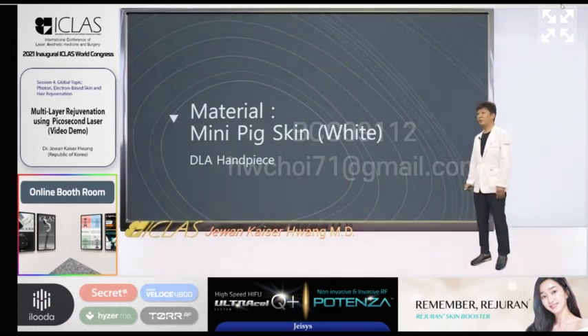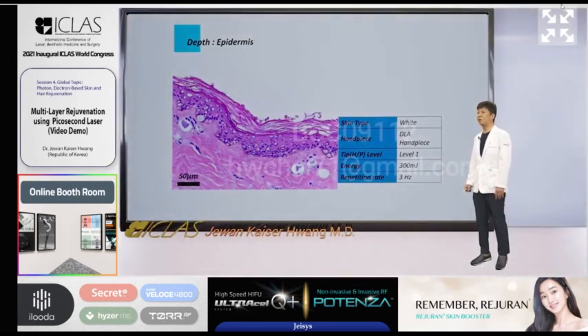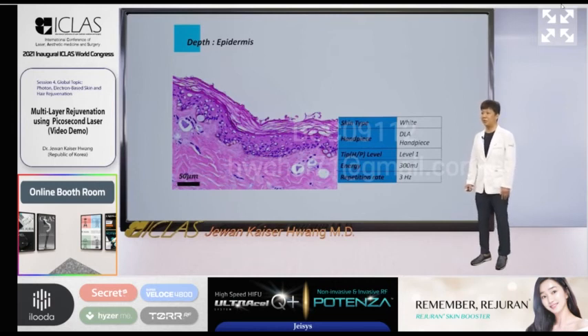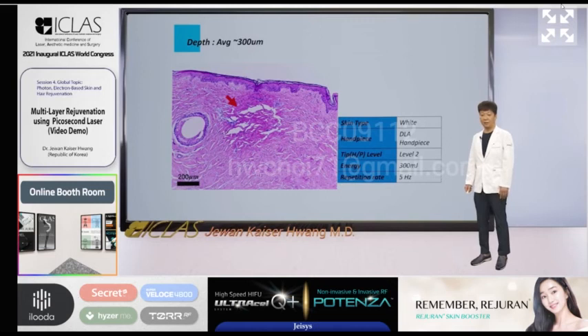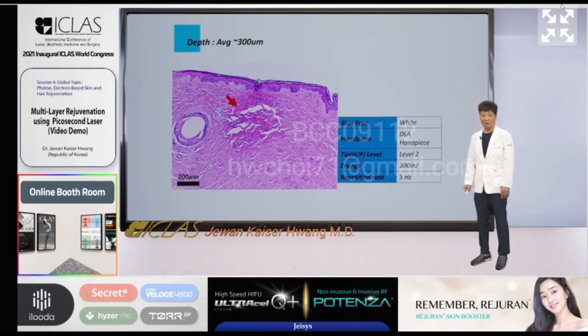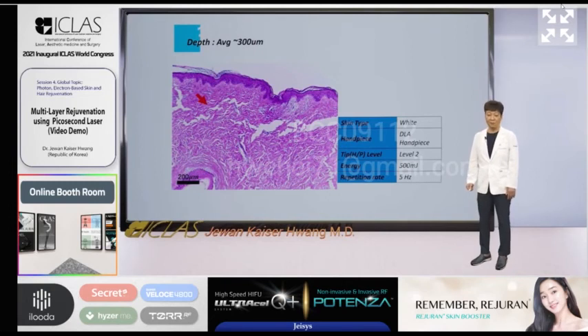It was tested on white porcine skin and black porcine skin respectively. The combination of focal depth and pulse energy can create cavitation in the epidermis using the DLA handpiece at tip level 1, energy 300 mJ, repetition rate 3 Hz. Cavitation can also be created in the papillary dermis by adjusting the parameters: tip level 2, energy 300 mJ, repetition rate 5 Hz. Another biopsy showed level 2 at 500 mJ and 5 Hz.